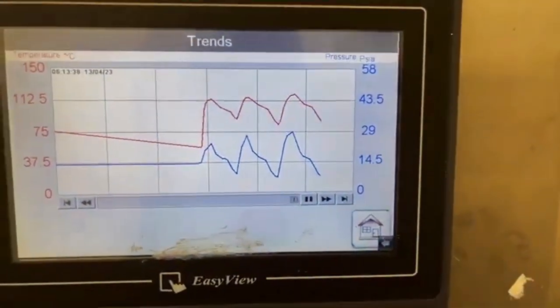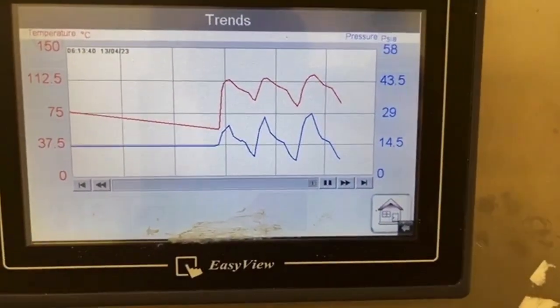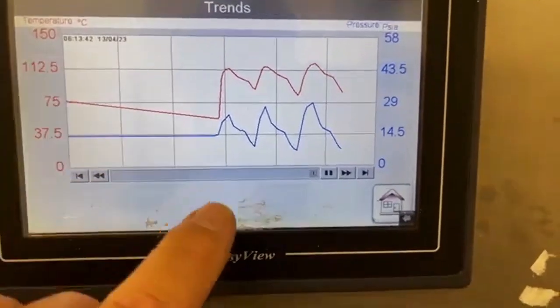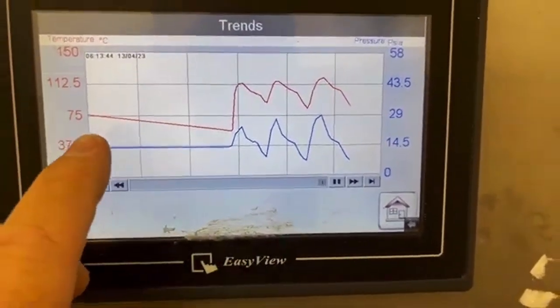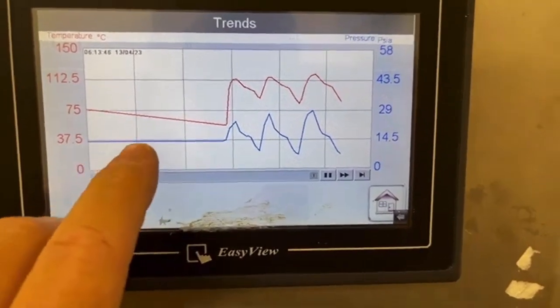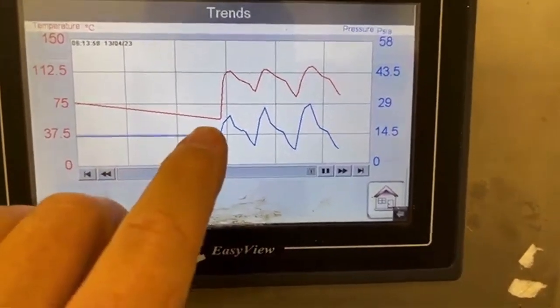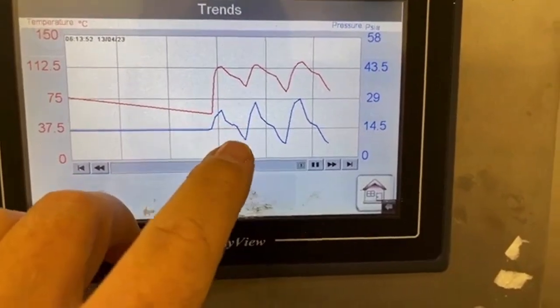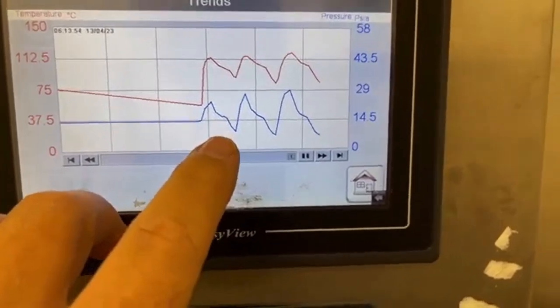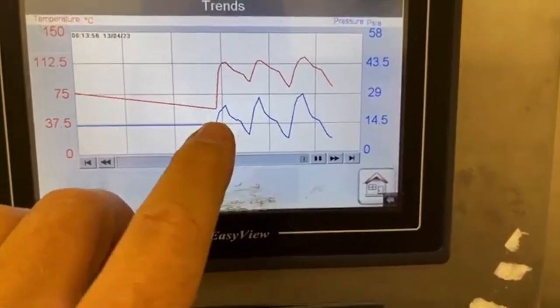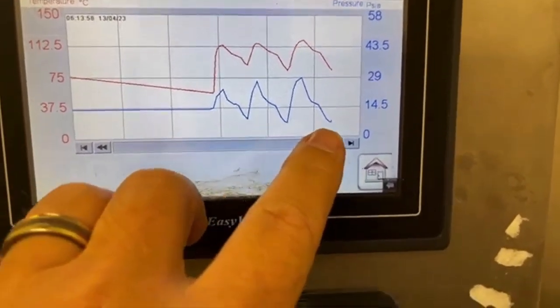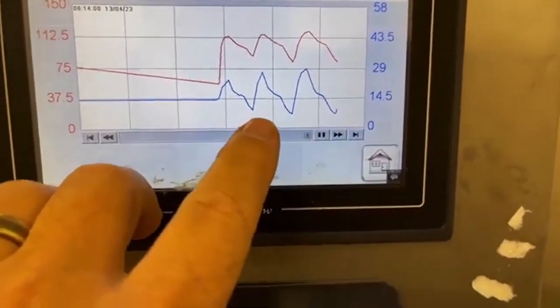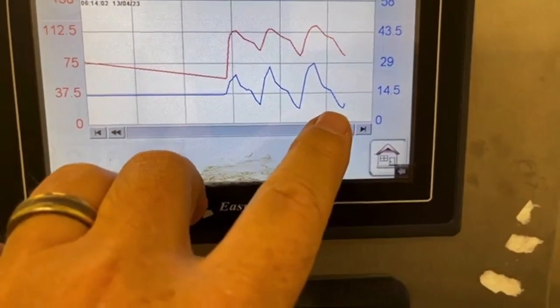I just want to jump in here very quickly. Here's a trends chart, and you're seeing the pulls here. This is where you're starting to purge. Things go down, temperature, and now you're starting to see the correlation with temperature, and then that's the pressure. And then you can see that this pull here and this pull here, the first one was light. These are definitely deeper pulls.